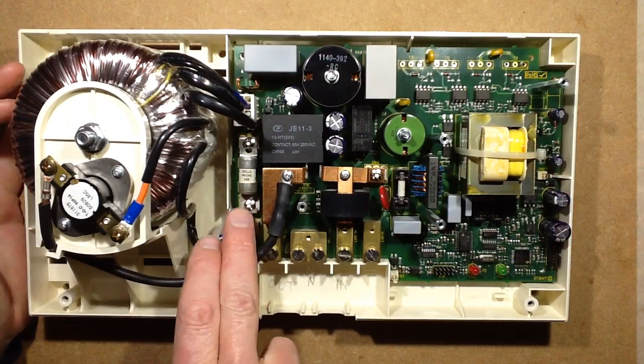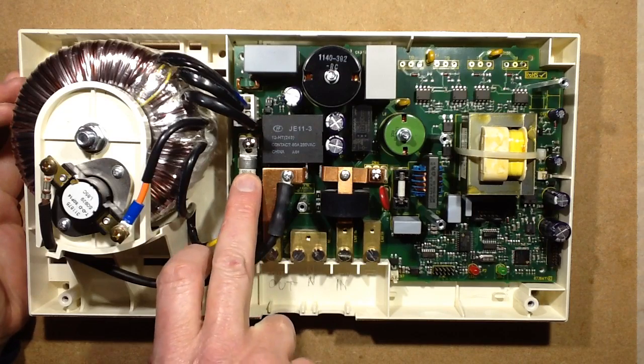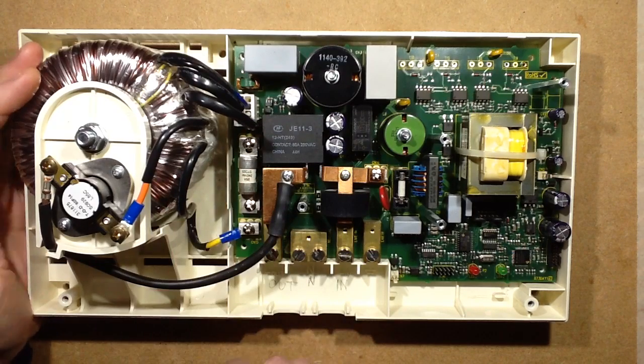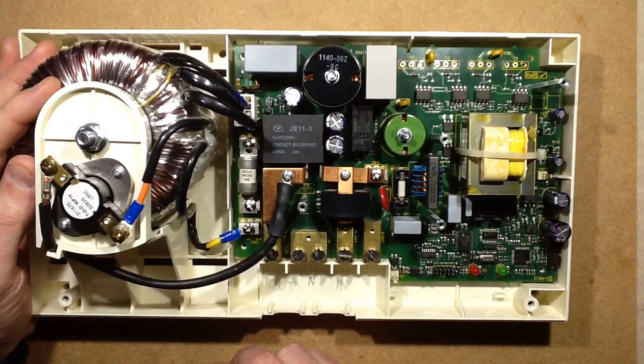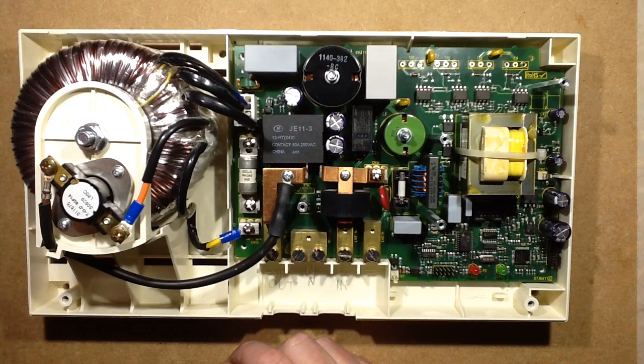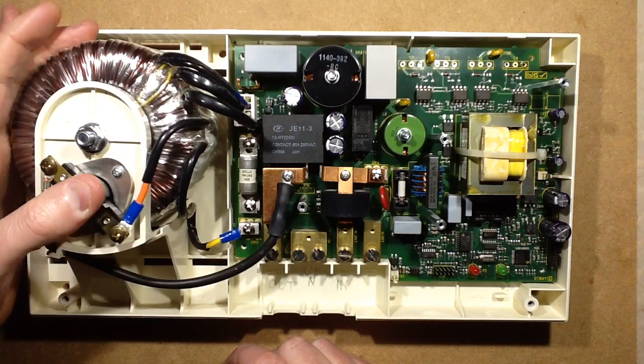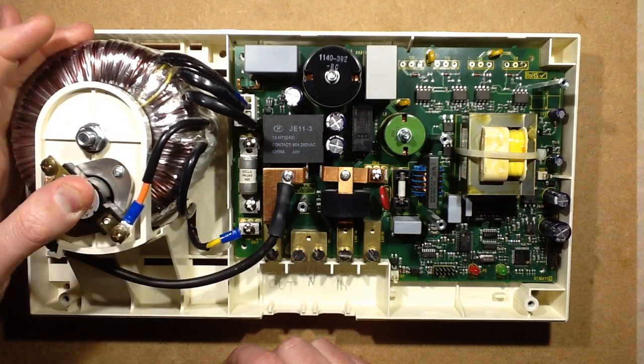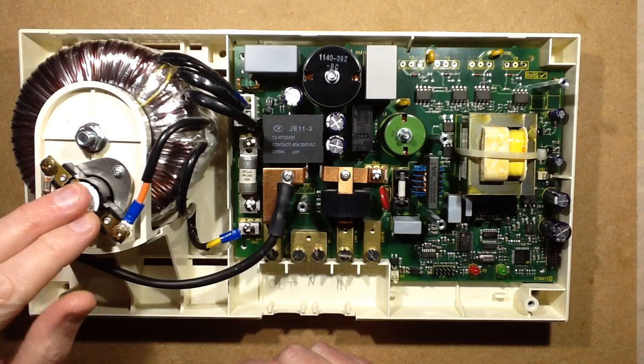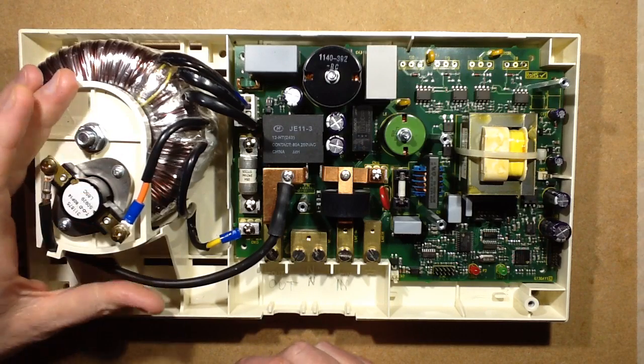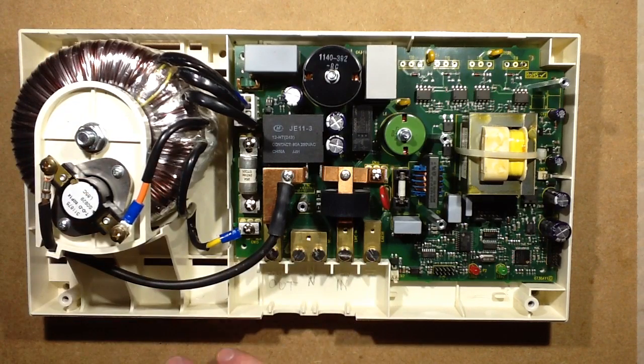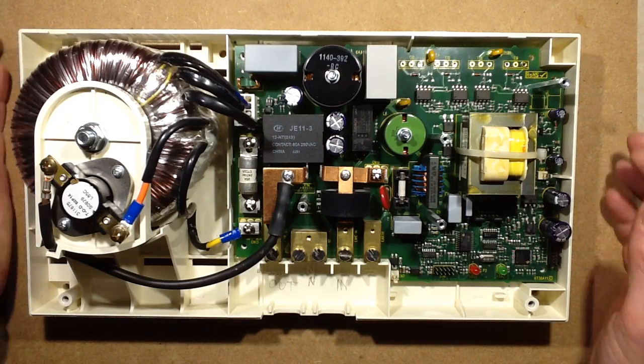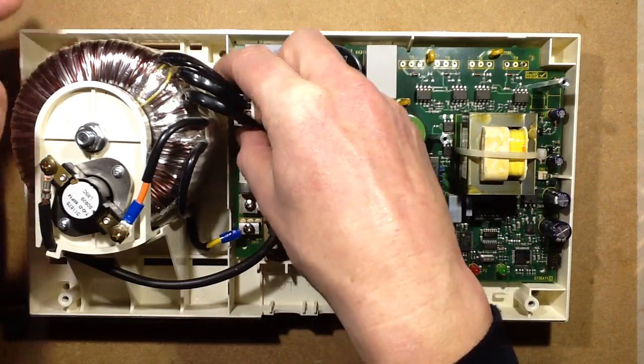And then of course there's this 25 amp fuse in line to limit short circuit current through the transformer, and then there's a big, huge, high current thermal cutout sitting on top with a thermal coupling onto the transformer itself, which will also cut out if a fault occurs and it starts overheating. So lots and lots of circuitry.